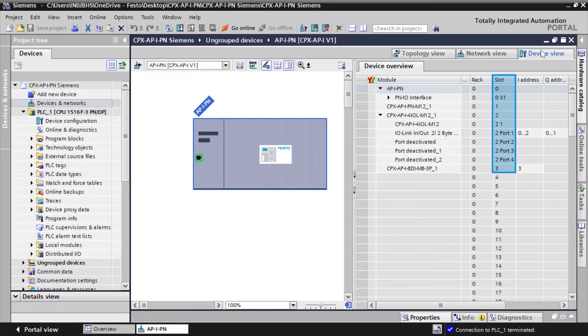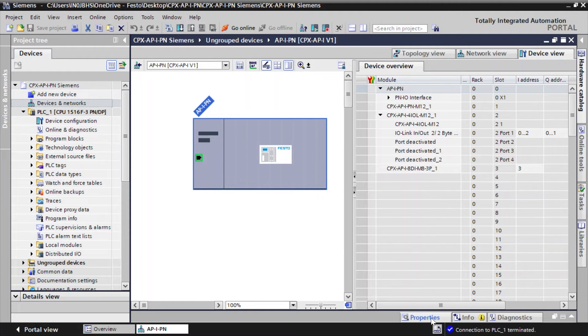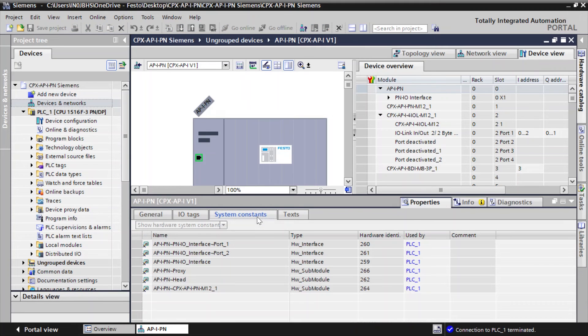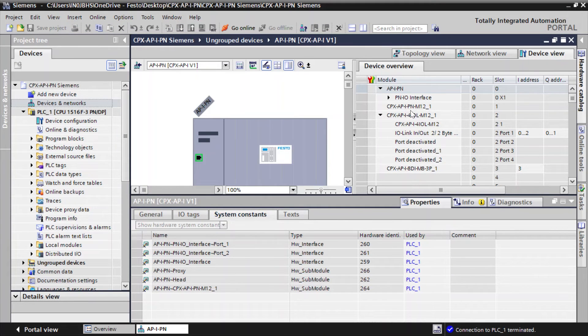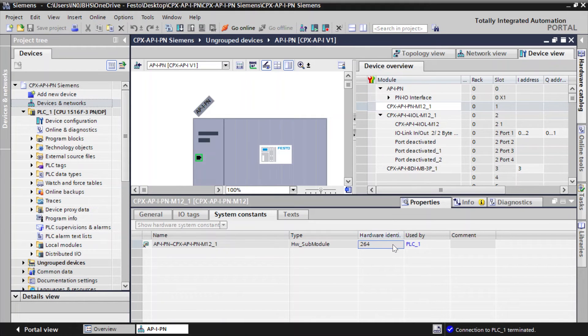Note down the slot number and sub-slot numbers of CPX-AP devices which are relevant for further commissioning. Click on Properties. Go to System Constants tab. Note down the hardware ID of CPX-AP devices which are relevant for further commissioning.